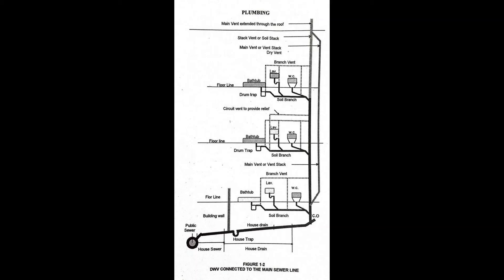Stack group is a term applied to the location of fixtures in relation to the stack so that by means of proper fittings, venting may be reduced to a minimum. Stack vent is the extension of a soil or waste stack above the highest horizontal drain connected to the stack. Stack venting is a method of venting a fixture or fixtures through the soil or waste stack.